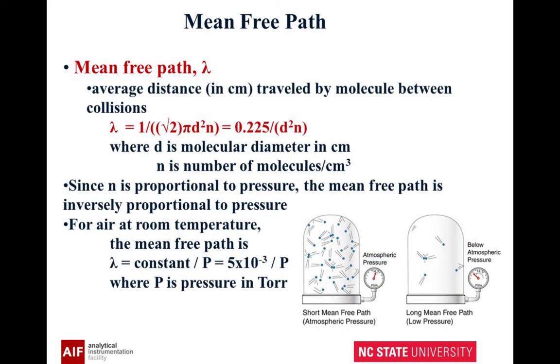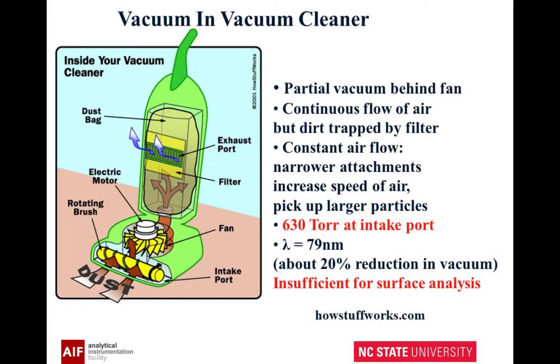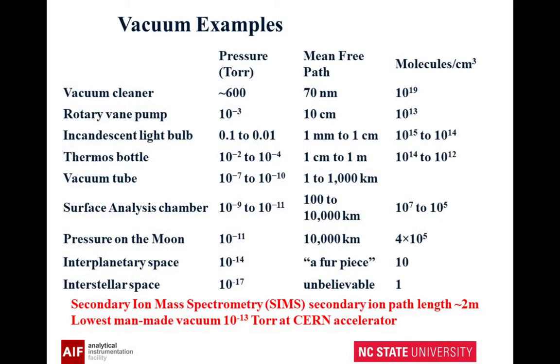Mean free path — this is another important concept. This is the average distance you travel between collisions. For air at room temperature, we can use a simple equation. Let's check out the mean free path. How about a vacuum cleaner? We've actually taken a vacuum cleaner and measured it. Your normal atmospheric pressure is 764 torr. The vacuum cleaner shows 630 torr, and the mean free path is 79 nanometers — so that's not going to work. For a rotary pump, the mean free path is about 10 centimeters.